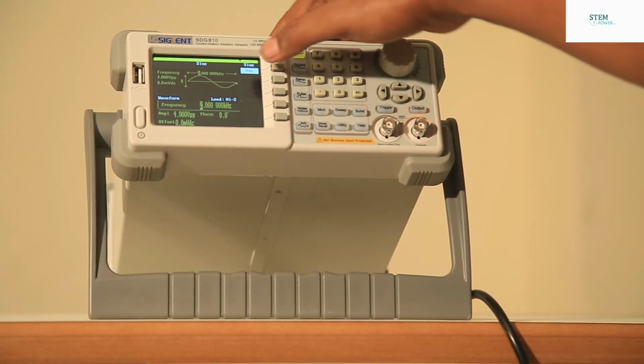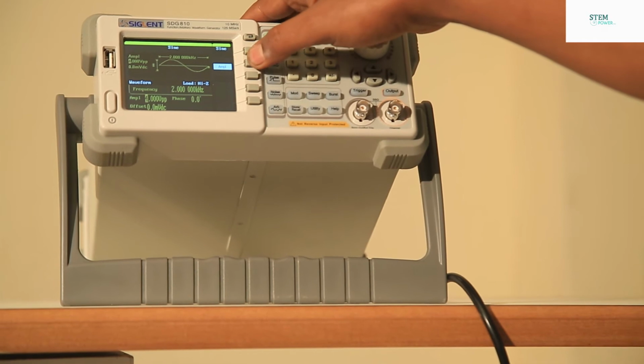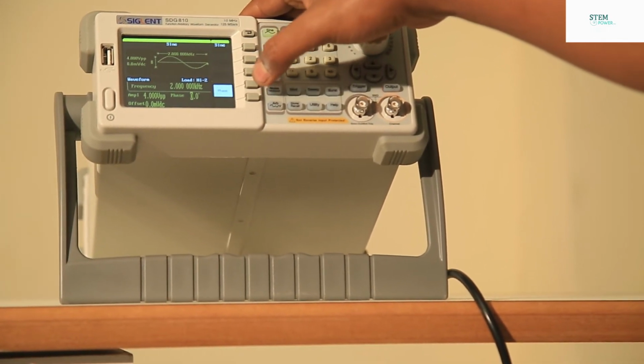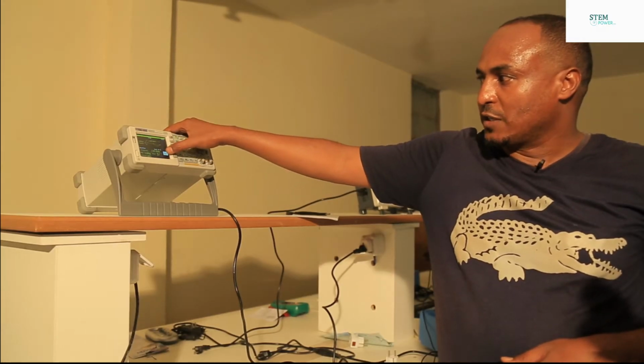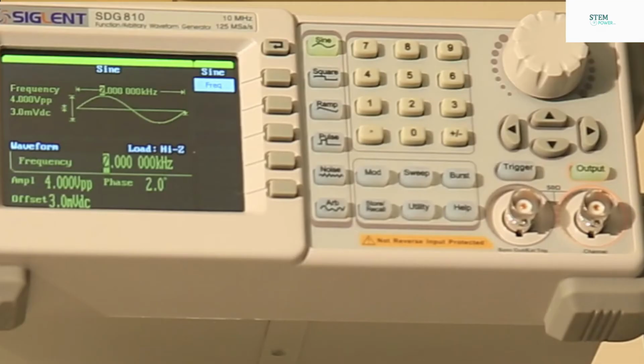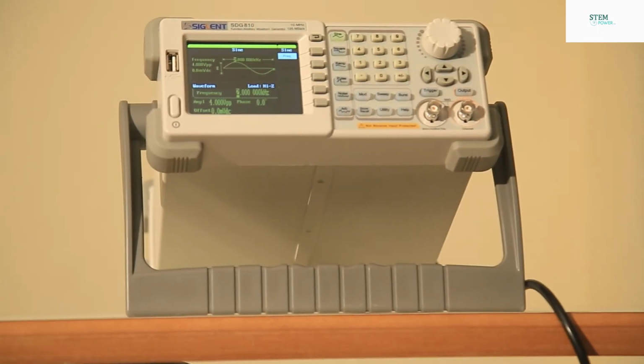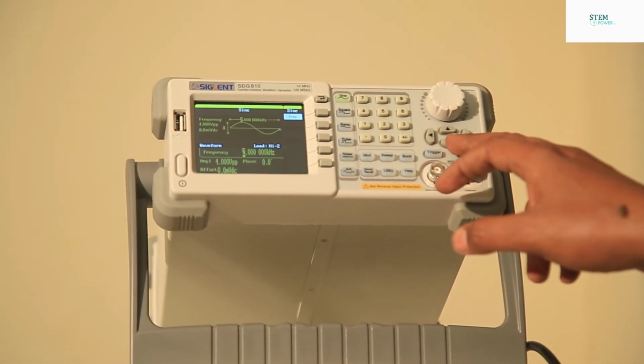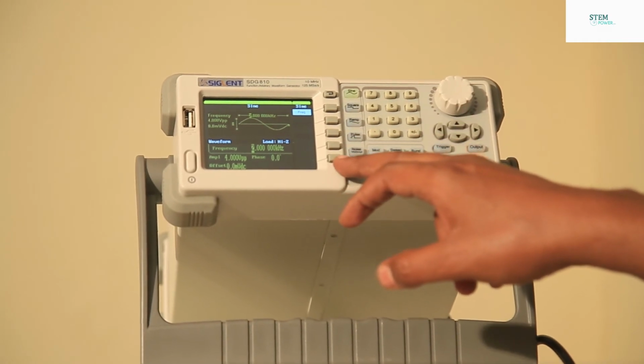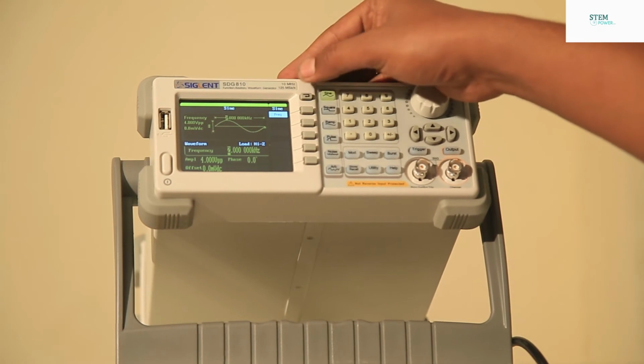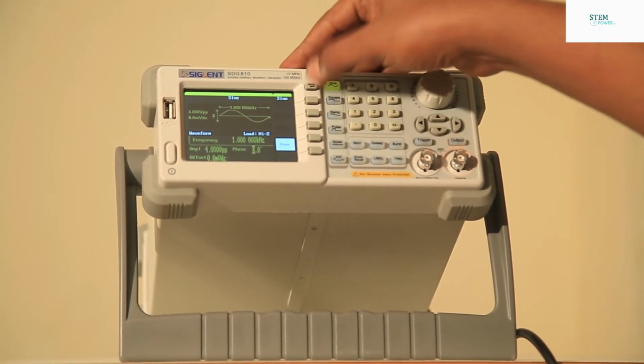Next, there are different parameters you can select here by pushing buttons: amplitude, offset or low value, phase, and so on. When you push the phase button, the phase segment on the display is highlighted, and then using the numeric keys, the knob, or the arrows, you can adjust or move the value. After selecting the parameter you want to calibrate or set, you use the up and down arrows or push the button, and this button lets you go back if needed.